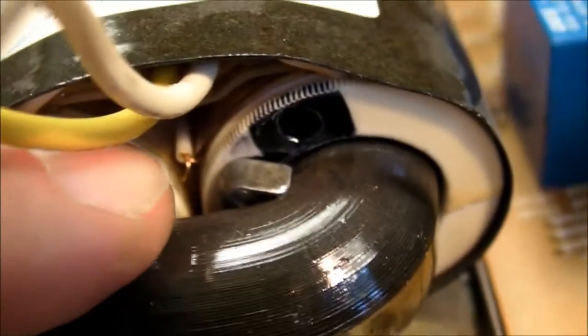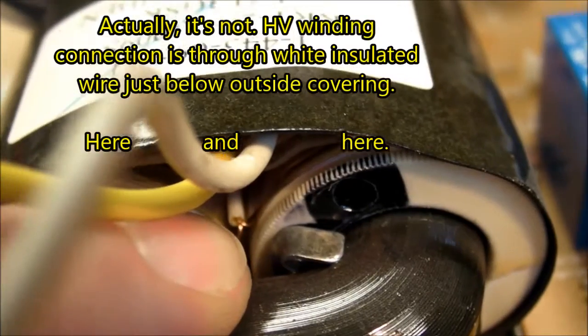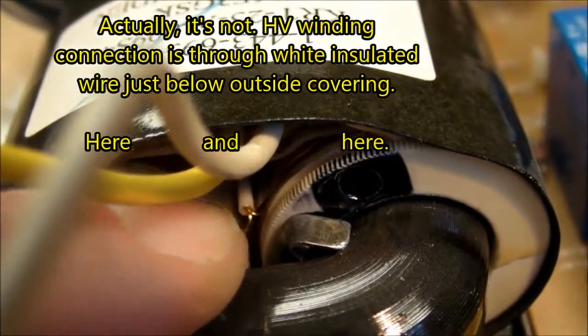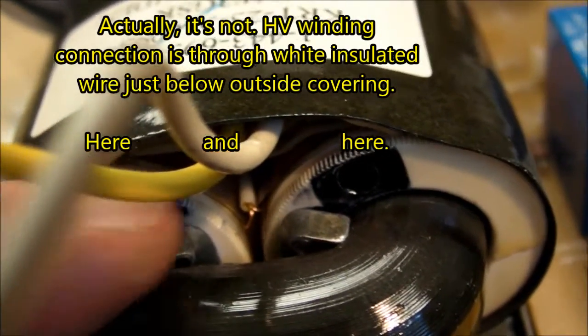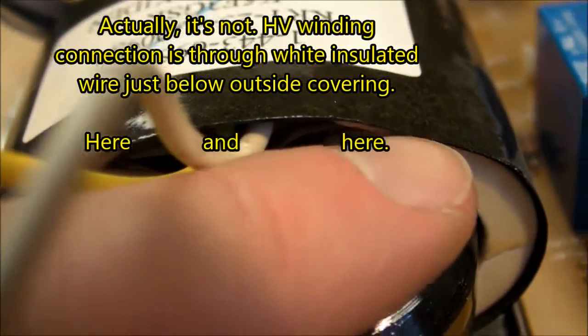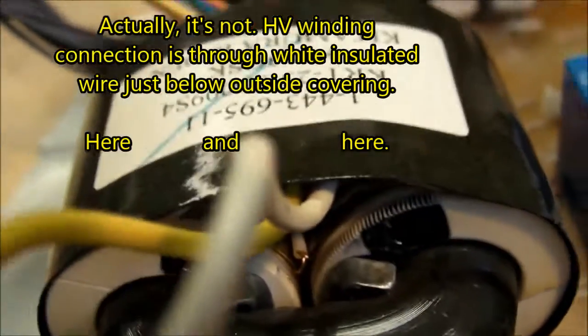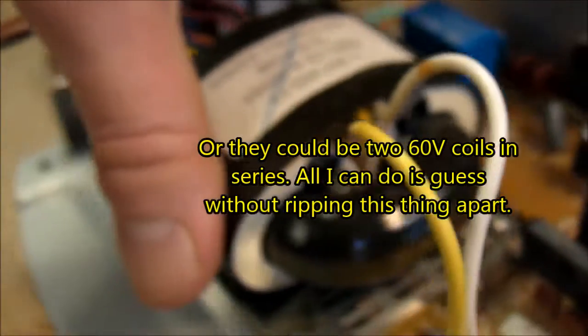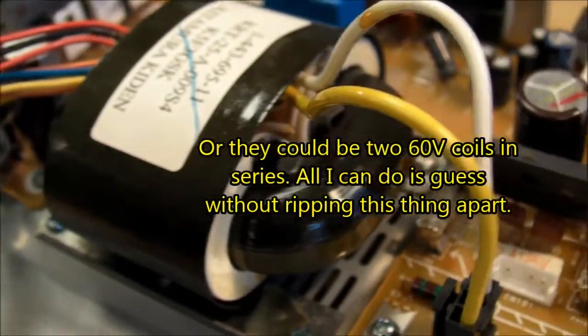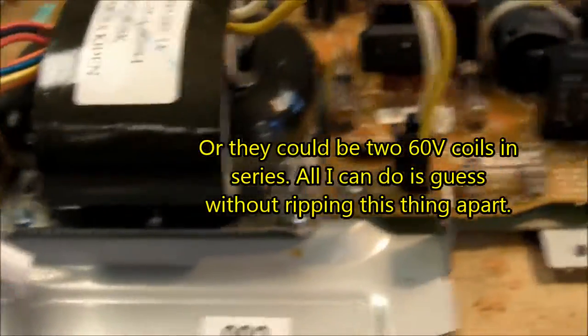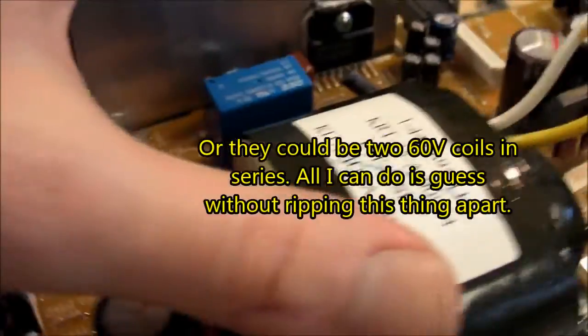And high voltage probably goes to both bobbins too. I would imagine that's the high voltage line right down in there. It'll be wound one coil here on the inside and another coil on the inside of this one too, and that makes sense for worldwide distribution. This one is wired for 120, but if you want to put it in a 240 installation, you just put both coils in series rather than parallel.